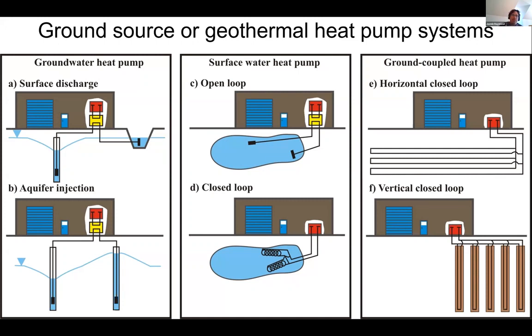If you want, the open loop system tends to be less expensive and have better performance if we compare the amount of boreholes that you need with the closed loop system, right? Just a few boreholes in a prolific aquifer can allow you to produce a high flow rate of water, and those systems can be very efficient, but they involve a little bit more maintenance and risk.